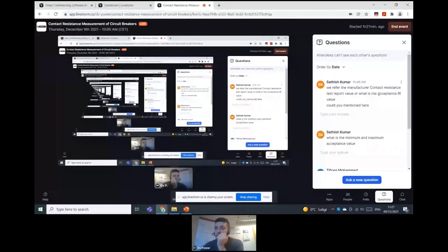For the contact resistance value which you should accept, or should expect, you should always refer to the manufacturer specifications. For all breakers, you will have expected limits. As I said, you can only have a problem with increased resistance. The manufacturer will give you acceptable limits for resistance. If you have only one expected value, usually for routine tests and type tests, 20% deviation is a limit. So you can put that as the reference.